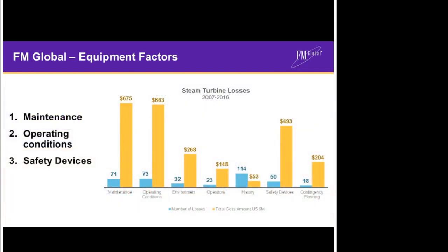Now, if we cast our minds back to those 183 steam turbine losses that cost FM Global approximately £1 billion over the last 10 years, this slide gives a clear indication of which equipment factors are driving those losses. The information gathered by engineers as part of their loss prevention consulting work prior to a loss, combined with post-loss investigation, enables identification of patterns and common denominators across losses. Analysis of this information shows that the three equipment factors where deficiencies have a particularly outsized impact are maintenance.